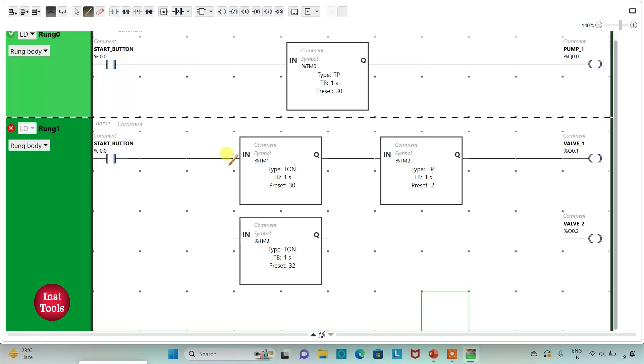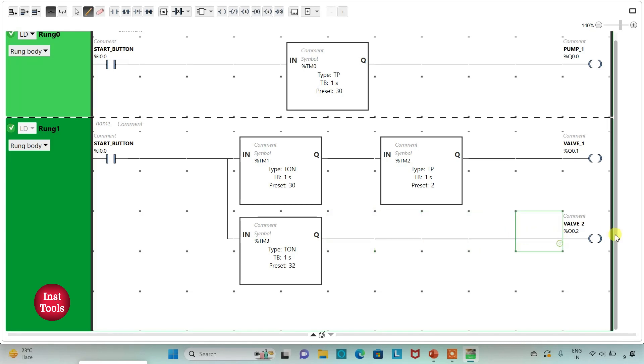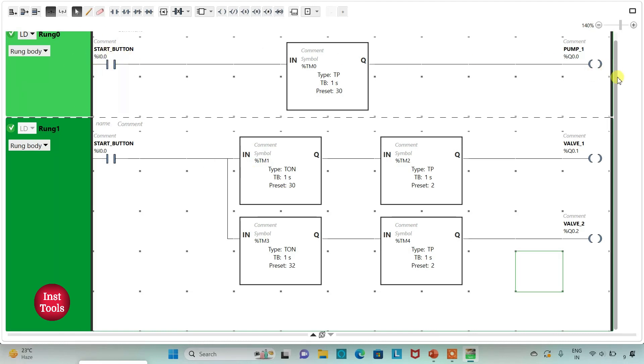Then I will connect it. Valve 2 will be activated after 32 seconds, but it should turn on for 2 seconds only, so I will use one more pulse timer. I will insert a TP timer for Valve 2, change the time base to 1 second and preset value to 2, then click Apply. So when the start button is on, Pump 1 runs for 30 seconds, then Valve 1 turns on for 2 seconds, and after 32 seconds Valve 2 turns on for 2 seconds.